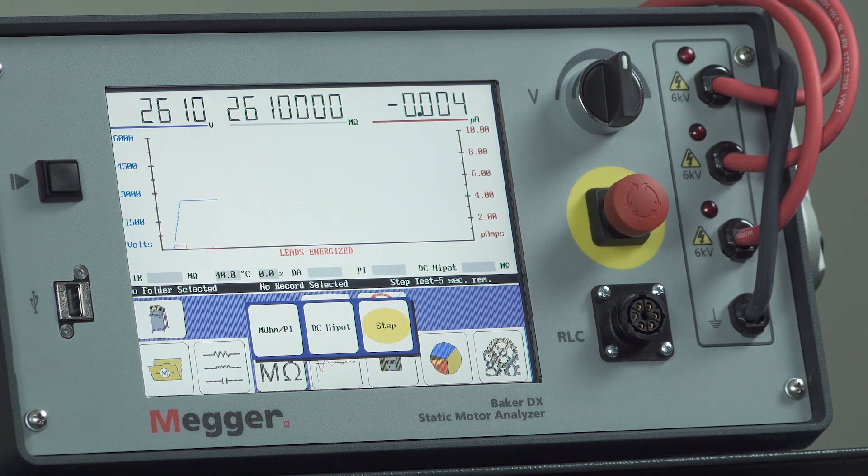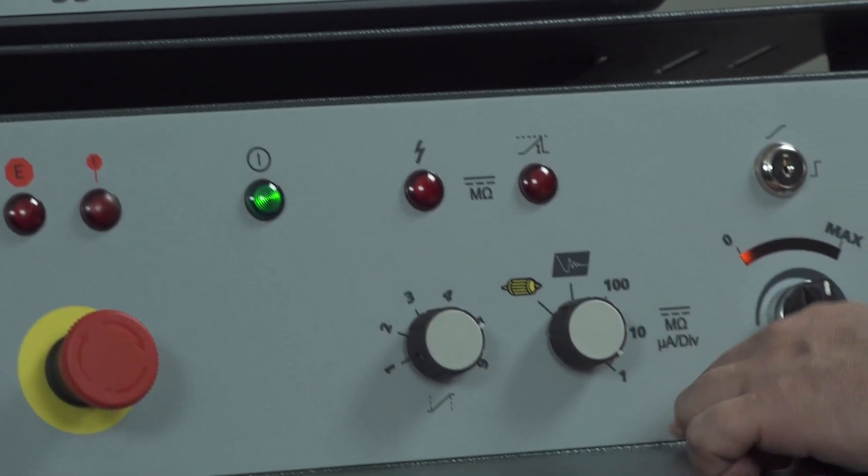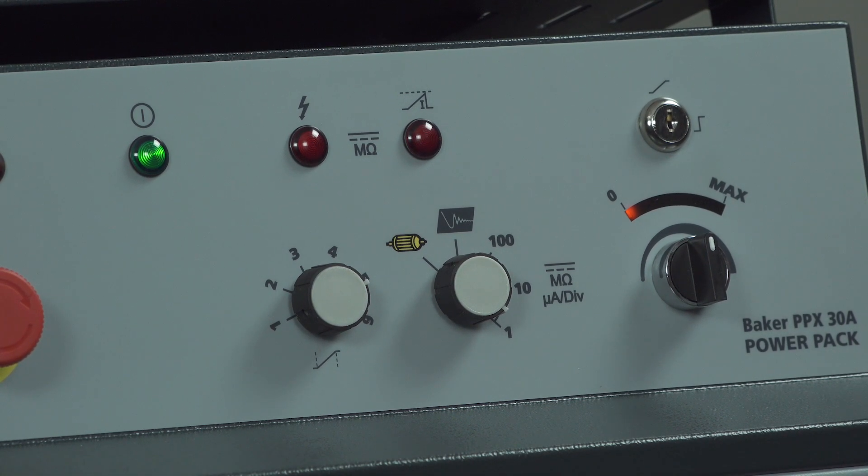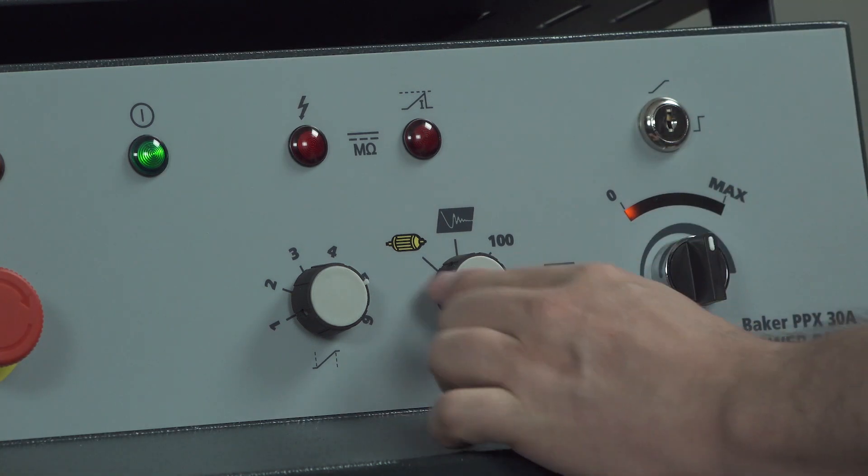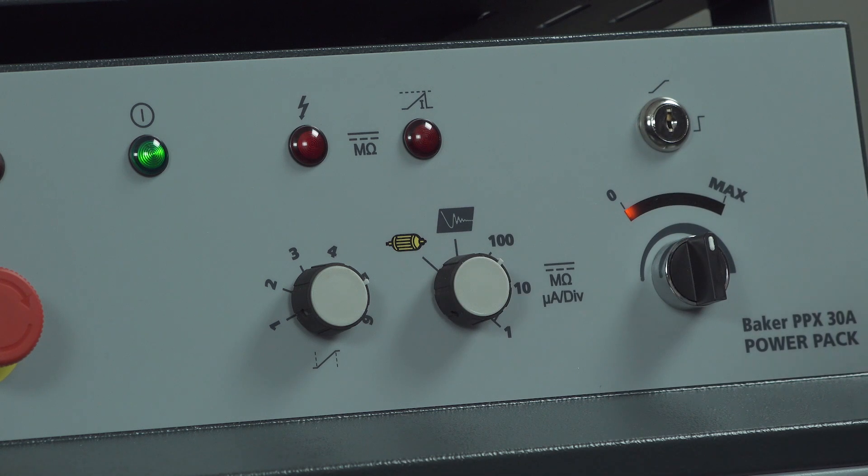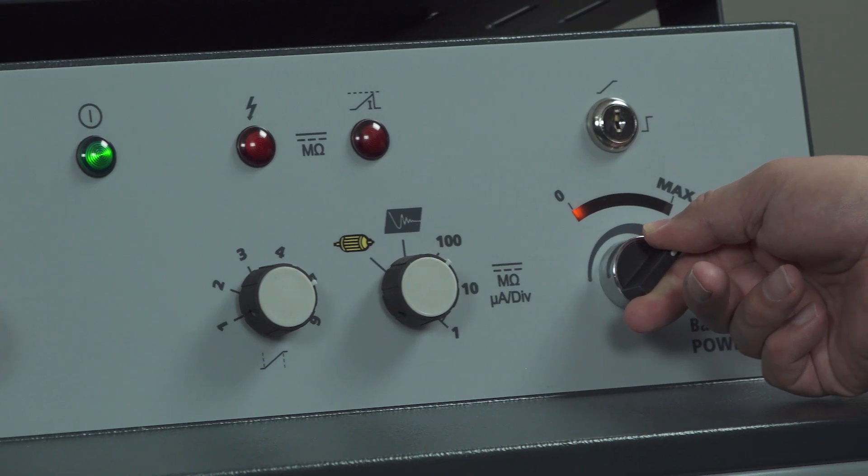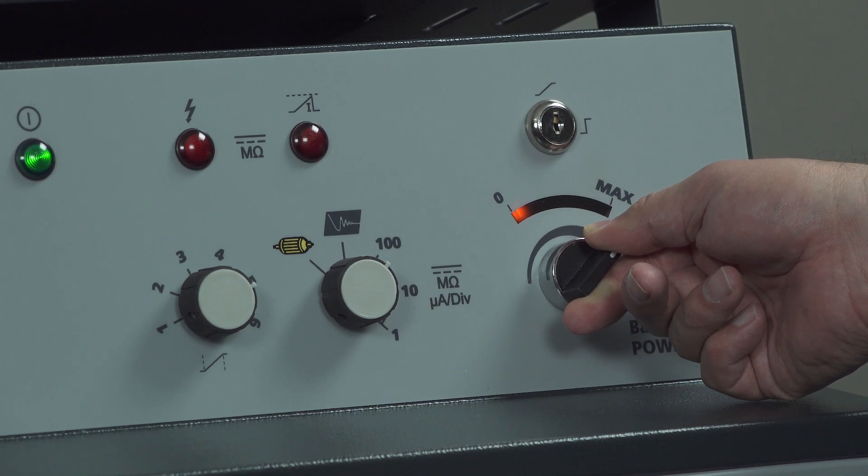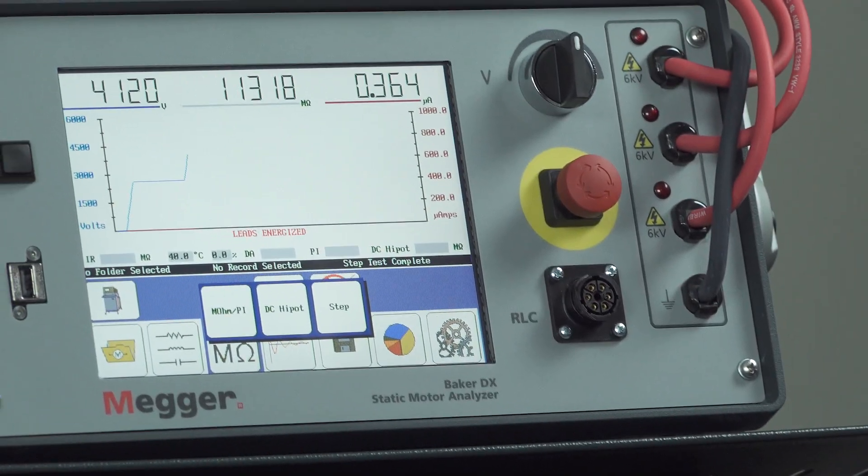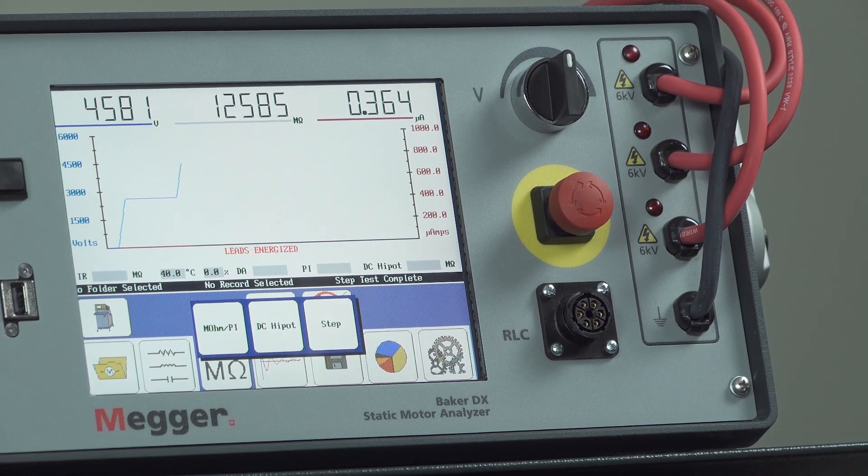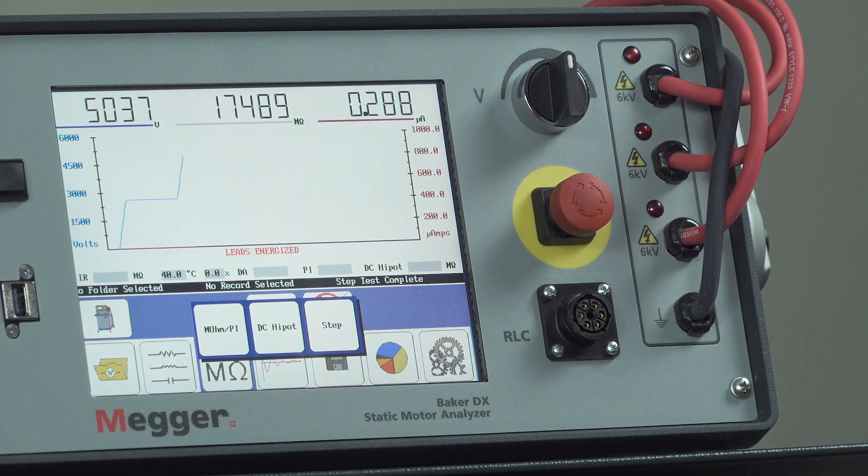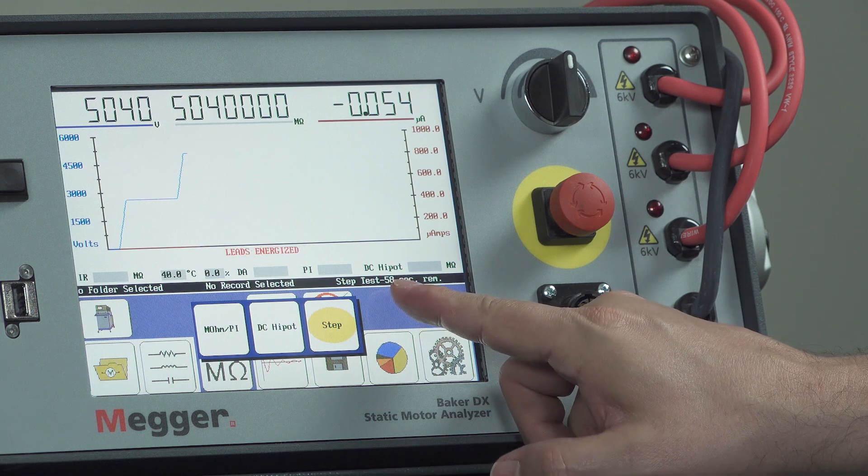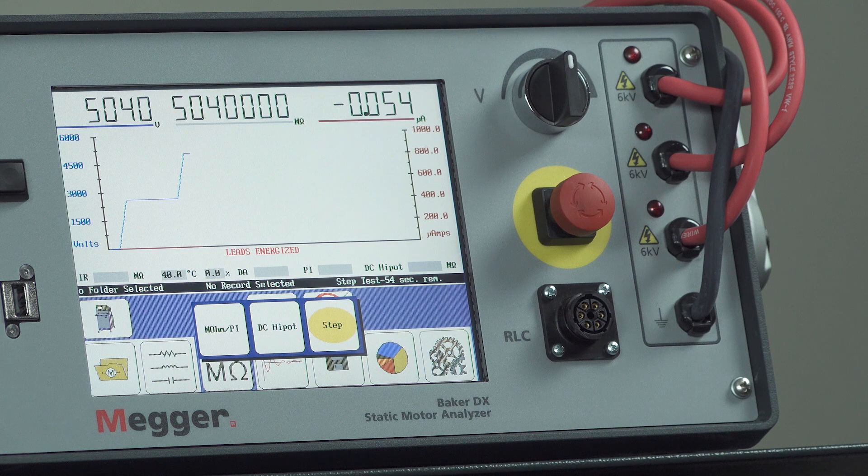Once the step time goes down to zero, it's going to say step test complete. We're going to make sure we take this function selector switch back to the 100 microamp per division setting, because these positions actually define the trip level of current. While we're ramping, the current level will be much higher during the ramping cycles. So it says step test complete. Take the function selector switch to the 100 microamp per division setting, and we'll use the voltage control knob to ramp to the next step, which will be 5,000. Now we're at 5,000. I want to hit the step button again. That tells the tester we're at a new step and we need a new timer. You'll see that timer up there on the right again.